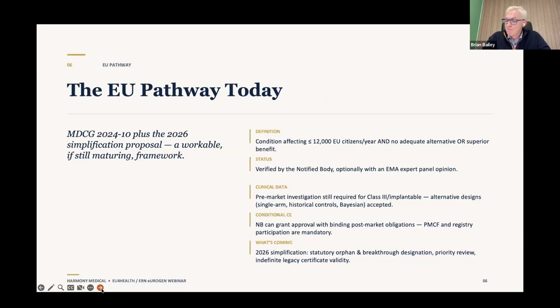So when we're talking about the new guidance, this really helps us because the clinical requirements are more proportionate. What that means is we don't need complex randomized controlled trials always. There's a conditional route to CE marking, I think is probably the simplest way to put it. It's a real improvement, but I do have two caveats. Firstly, it's only a guidance document and not legislation. And there still seems to be some confusion over how to implement it between the notified bodies. So in practice, predictability is still an issue.